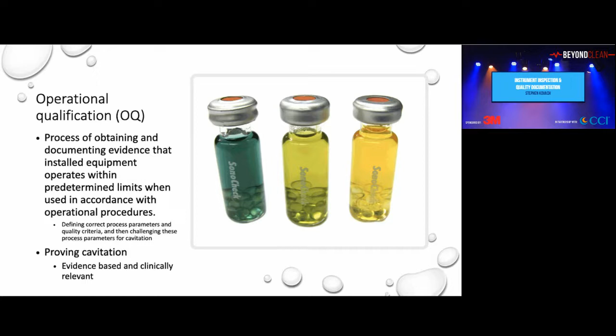You define the process parameters, the quality criteria, then challenge those process parameters for cavitation. You are proving cavitation. You will use evidence-based, clinically relevant products. Now, I do see some that use a foil test, and they install it. And when you use a foil test, there's nothing wrong with it, but you have to make sure you drain it, clean it. And if little foil broke off, you have to run some cycles to make sure there are no little foil pieces left, because if it comes back through recirculating, what if it gets on an instrument and sticks there and gets through and gets on a patient?